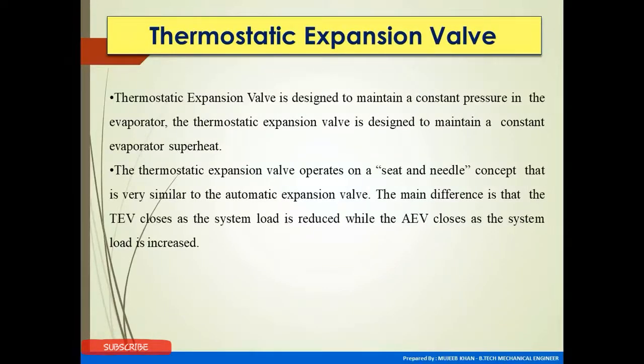The thermostatic expansion valve is designed to maintain a constant evaporator superheat. It operates on a seat and needle concept, which is very similar to the automatic expansion valve. The main difference is that the TEV closes as the system load is reduced, while the AEV closes as the system load increases.